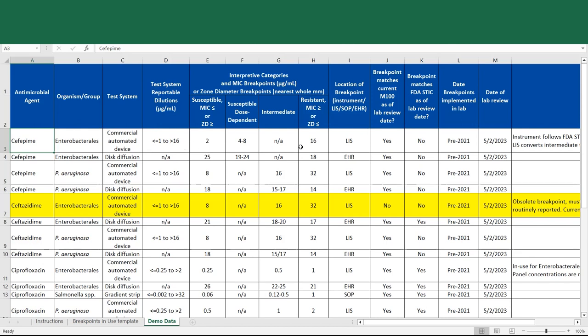It should be noted that both CLSI and FDA describe the resistance breakpoint as a greater than or equal to a value, in this case 16. But commercial devices sometimes report the highest value as greater than a certain number.